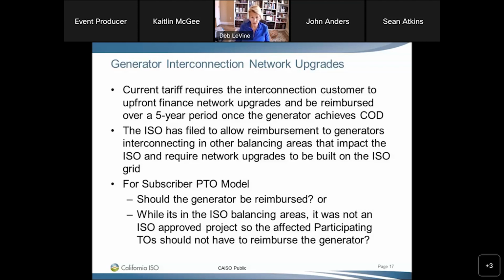A couple of pieces of information for people. The ISO, in the interconnection process enhancement for 2021, already filed with FERC to reimburse generators interconnecting in other balancing authority areas that impact the ISO grid. If there's a network upgrade required on the ISO grid, we would reimburse that generator in APS, Nevada, SRP, IID, or any bordering balancing authority areas.